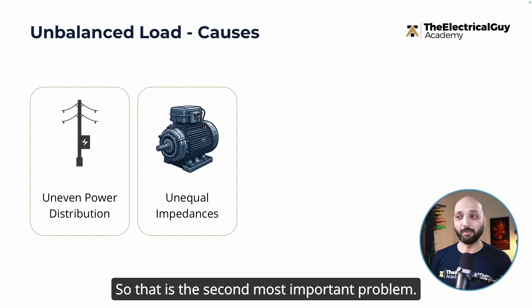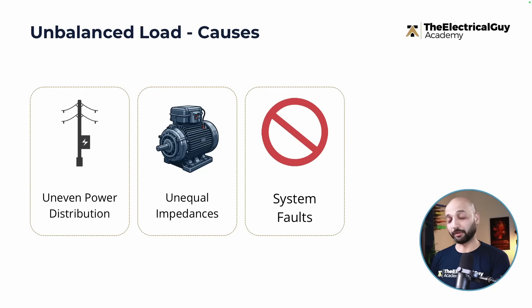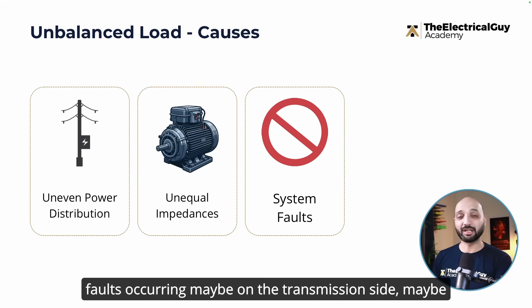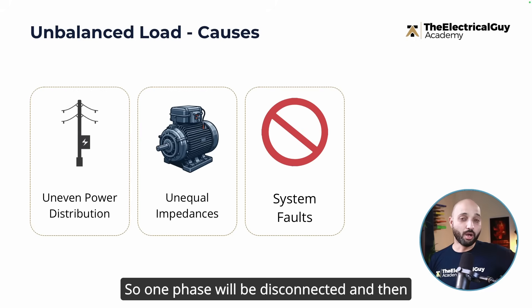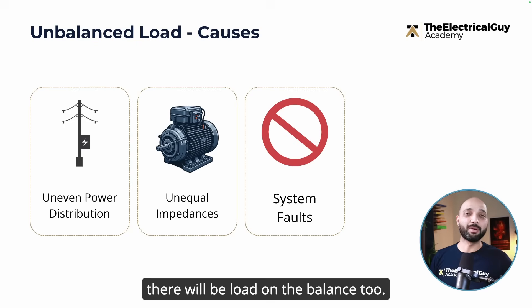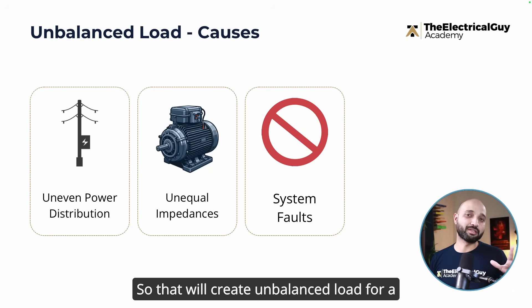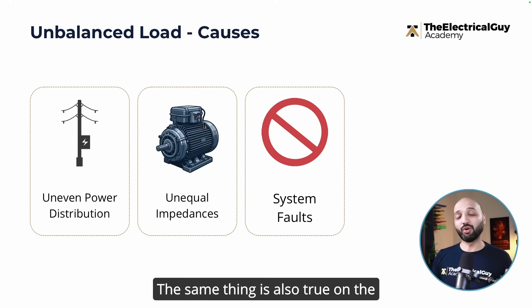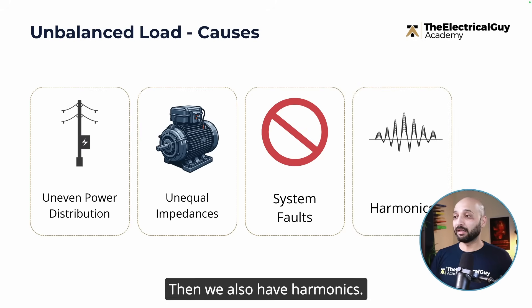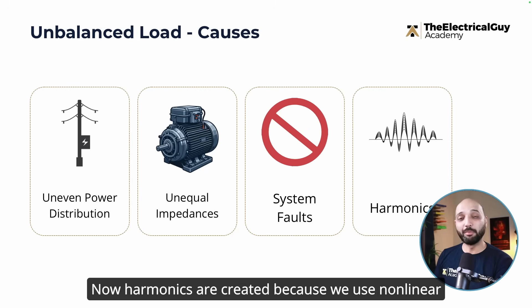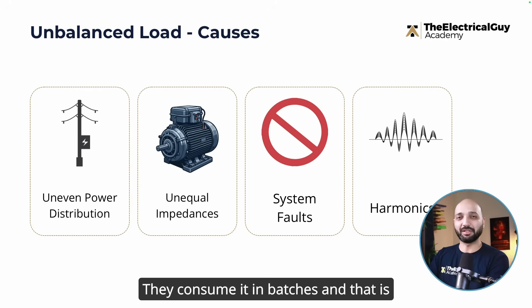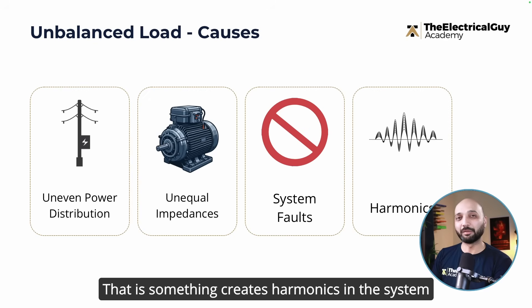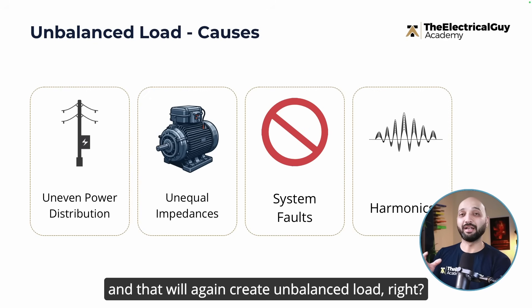The third cause is system faults. Faults can occur on the transmission or distribution side — for example, a single line-to-ground fault disconnects one phase and creates an unbalanced load for a brief period. The fourth cause is harmonics. Harmonics are created by non-linear loads such as computers and variable frequency drives, which don't consume current at a constant rate but in batches. This creates harmonics in the system and again produces unbalanced load.